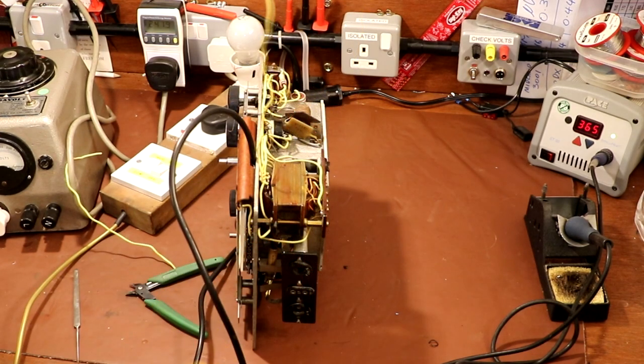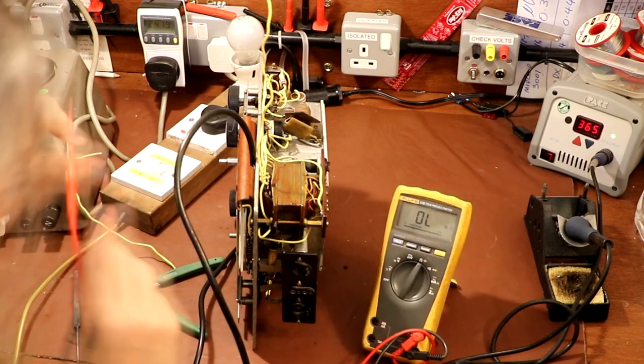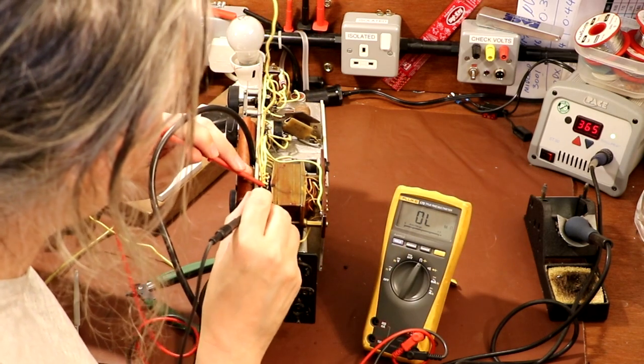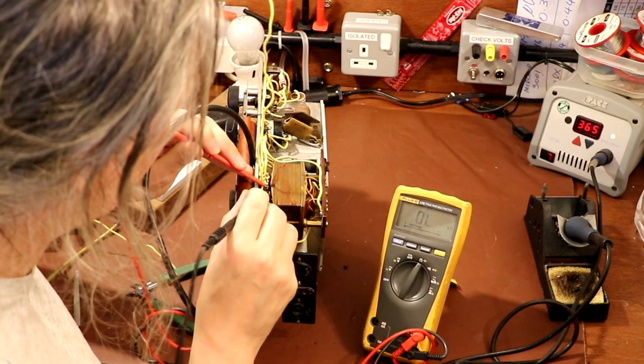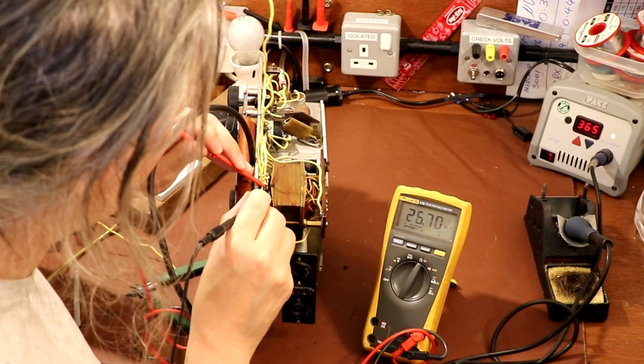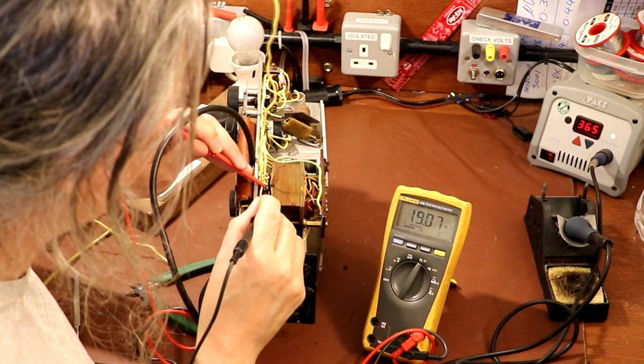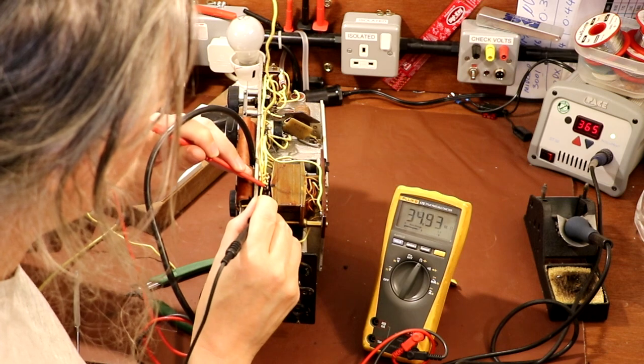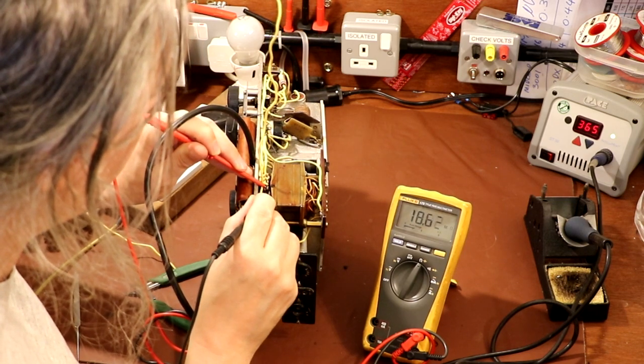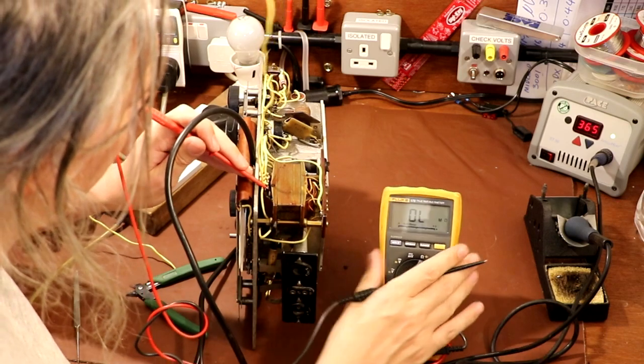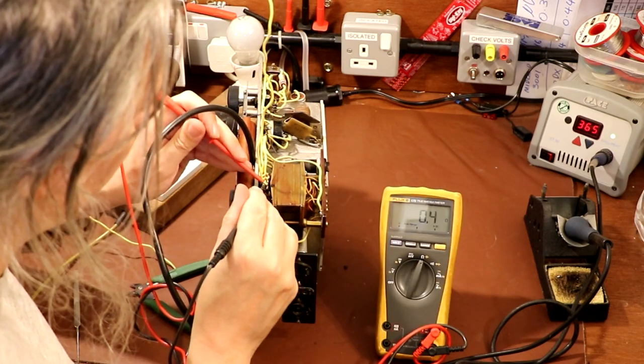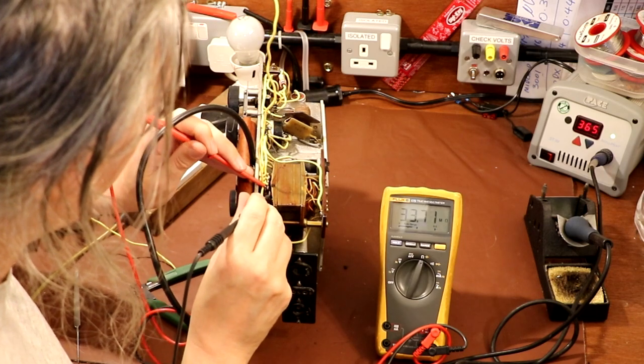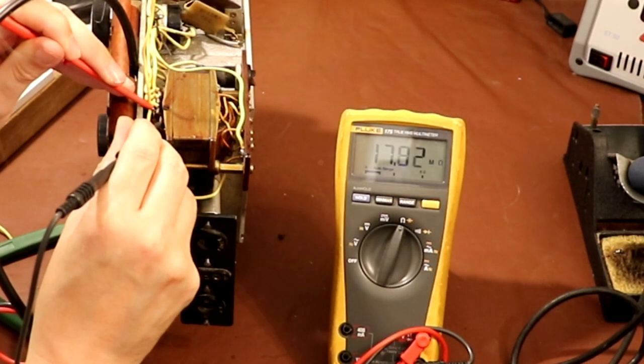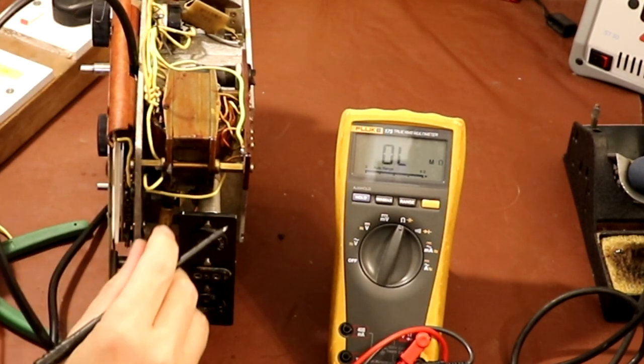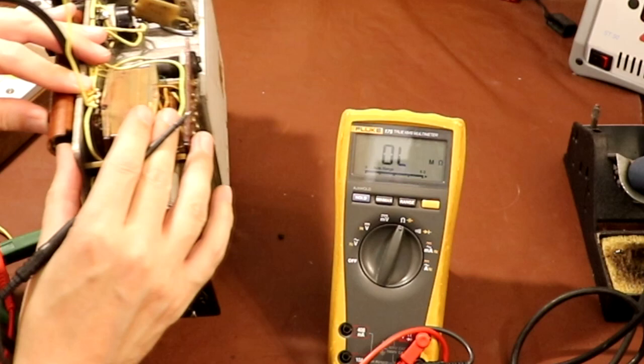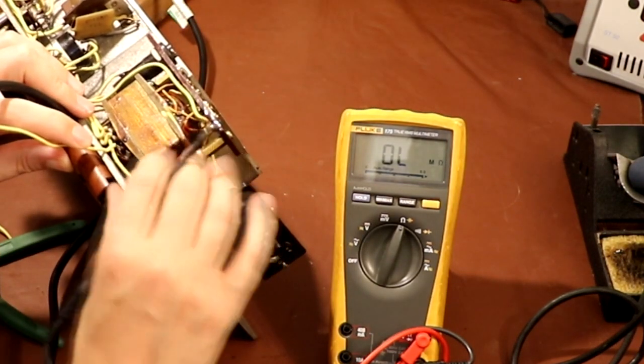I would have thought we should see a few hundred ohms across the secondary of the transformer. Come on, come on, come on. See some resistance. No. No, you see, we're seeing on the meter here, we're seeing lots and lots of megs. Let me just test my meter, 0.4 ohms. We're getting 17 meg ohms.